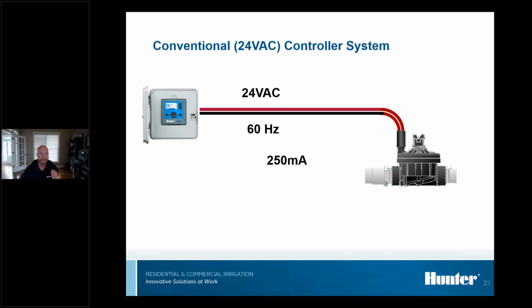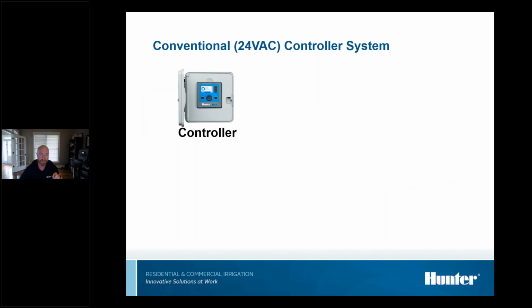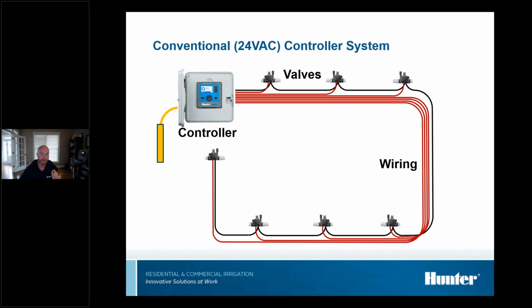So with a conventional 24 volt AC controller system, like we talked about, I'm going to reiterate this. You get 24 volts at 60 hertz. The flow in amps is 250 milliamps, or 0.25 amps. This is a conventional system. Just like we talked about, you've got a wire for every valve. So you've got your controller, a dedicated wire for every valve, and then that black wire is a common wire.